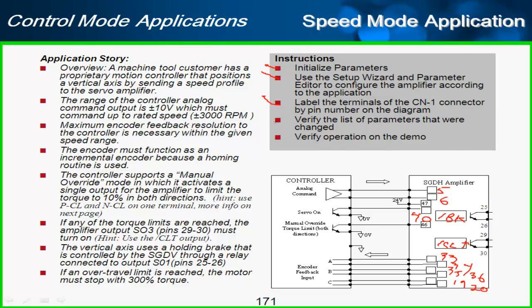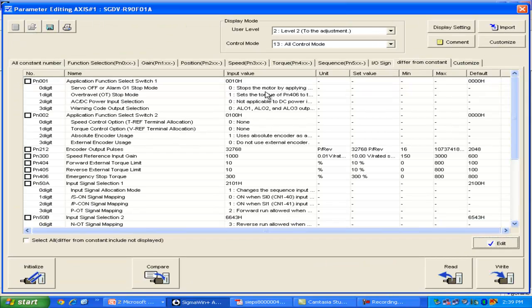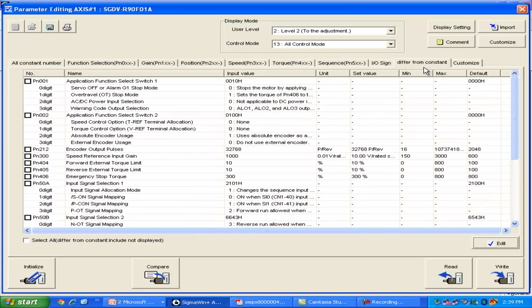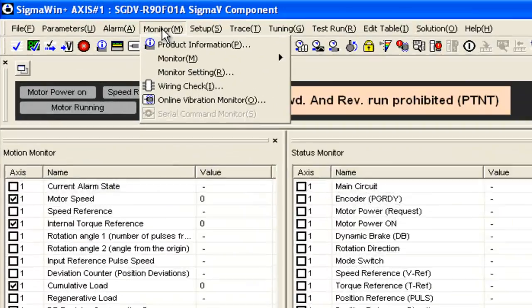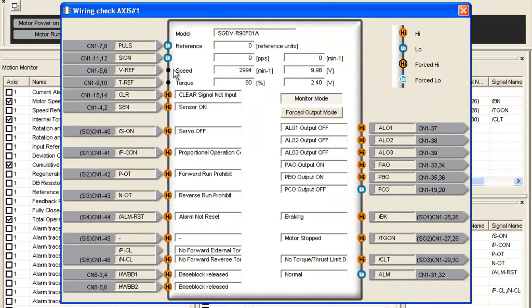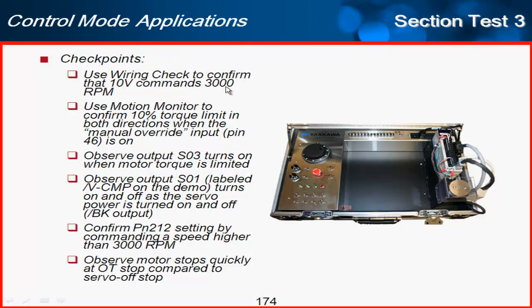Encoder feedback is the same for every application: PAO, PBO, PCO on pins 33, 34, 35, 36, 19, and 20. That finishes my labeling. To see a summary of changed parameters, I'll go to the parameter editor and look at the 'differ from constant' tab, which shows which parameters have been edited from default. Then I'll check operation: I'll confirm the wiring check shows that 10 volts commands approximately 3,000 rpm.